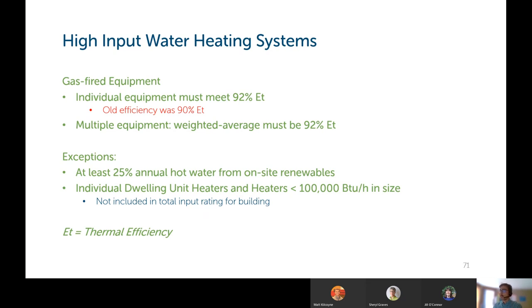There are some exceptions to needing to meet that requirement. If at least 25% of the annual hot water comes from on-site renewables, your gas-fired equipment doesn't need to be 92% efficient. Individual dwelling unit heaters and other small heaters less than 100,000 BTU per hour are not included in the total input rating of a high input water heating system. Those are just going to be included in the smaller individual sized unit requirements.